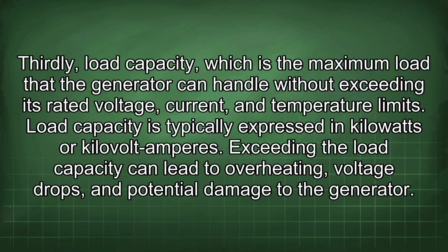Thirdly, load capacity, which is the maximum load that the generator can handle without exceeding its rated voltage, current, and temperature limits. Load capacity is typically expressed in kilowatts or kilovolt amperes. Exceeding the load capacity can lead to overheating, voltage drops, and potential damage to the generator.